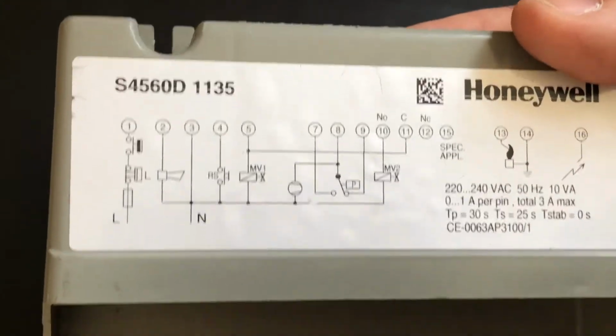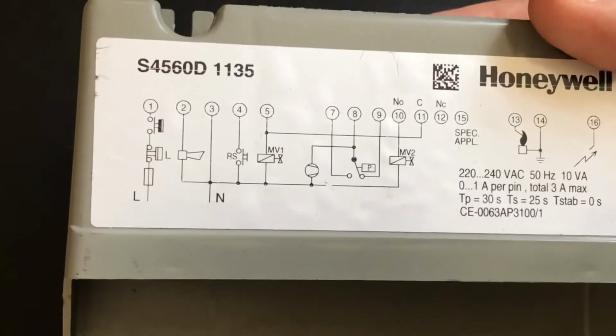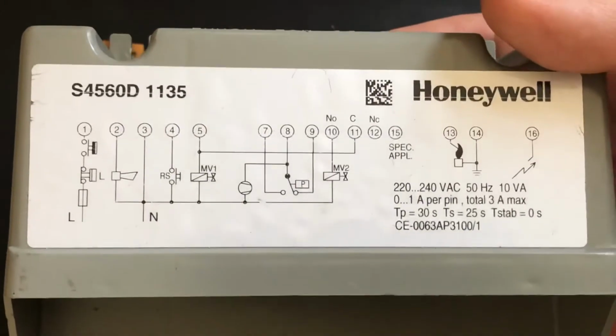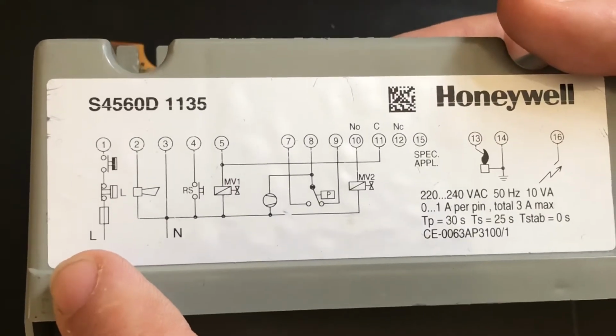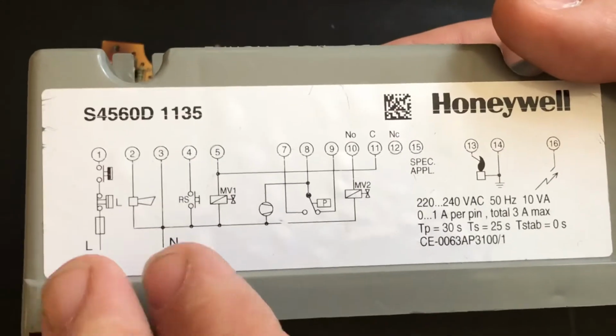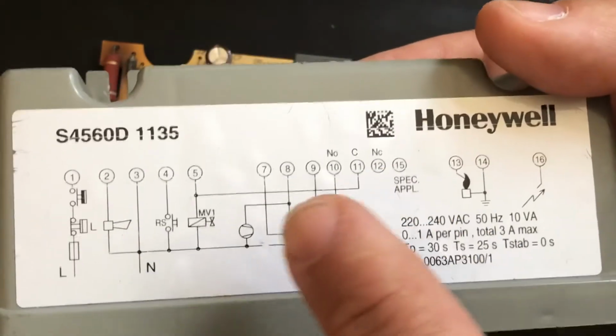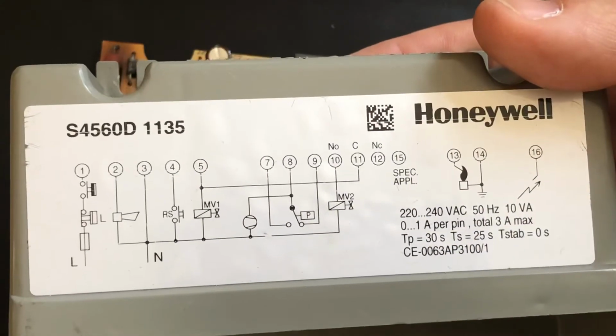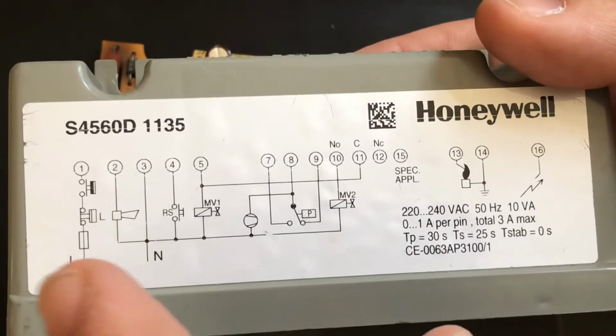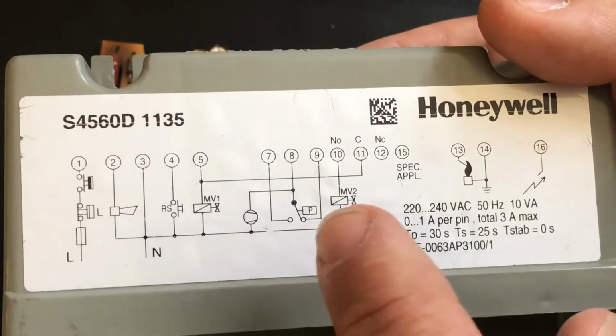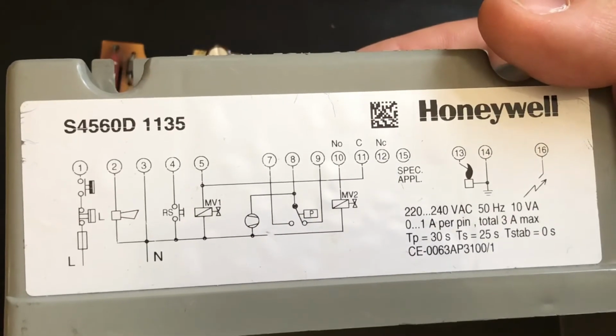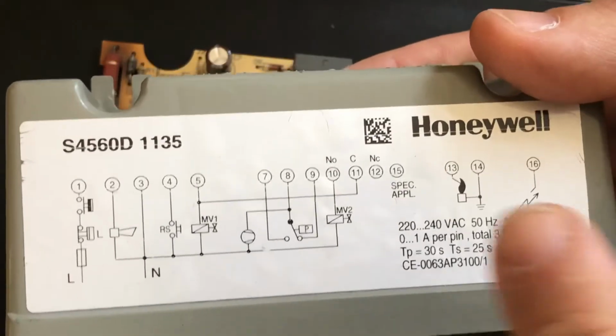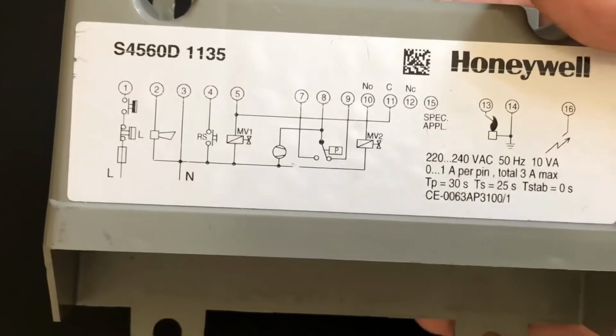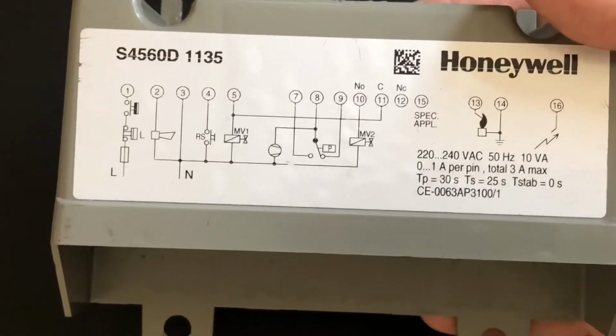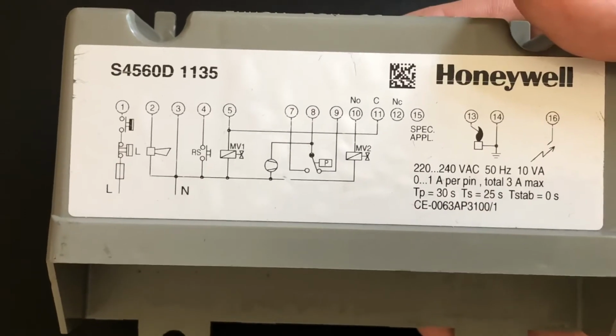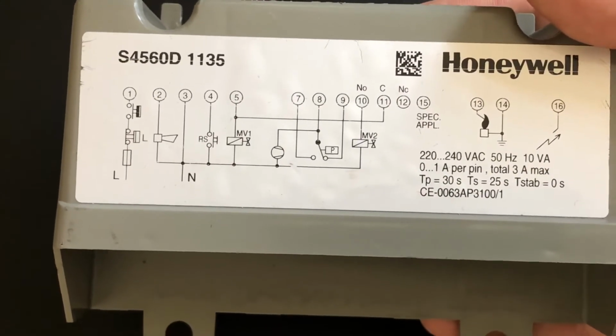If you do everything right and this one doesn't work, then yes, it might be an internal fault. But what you have to remember is to have power supply to L, live, and neutral. So I suggest you check first if the circuit 8 and 9 are in short. I mean, if you have a closed circuit between 8 and 9, and when you apply L, then the fan will work, and then it will close the circuit between 8 and 7, and then the ignition will start. So please do not spend a lot of money. It's 180 pounds for one of these units, and I've seen so many people being ripped off, and that upsets me, because they spend a lot of money.